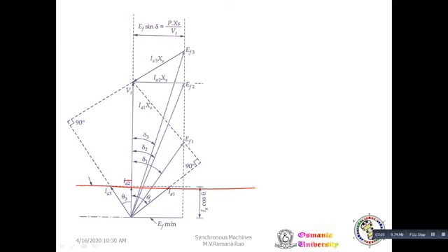Whereas current is initially reducing. Again, from this point, it is increasing. So as we go on increasing the excitation, current reduces to a minimum current, and again current increases. Still, if we go on increasing the excitation, current increases. The minimum current occurs at unity power factor.